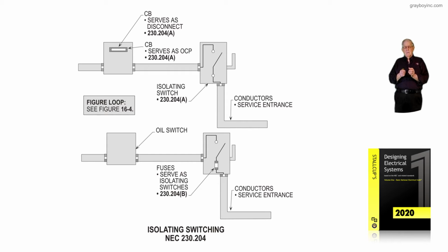and there's a warning label required to be on that switch. Warning, do not disconnect under load. But after the load has been disconnected, that isolation switch is ahead of it, then you could disconnect and lock and tag it out, in accordance with Article 120 of NFPA 70E, and it could serve as a non-fusible disconnect for isolating an area.